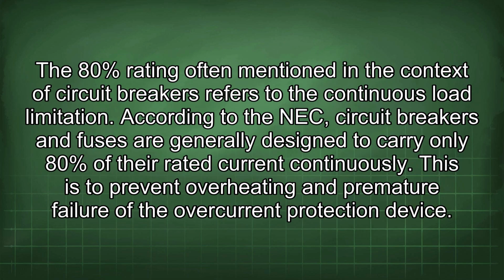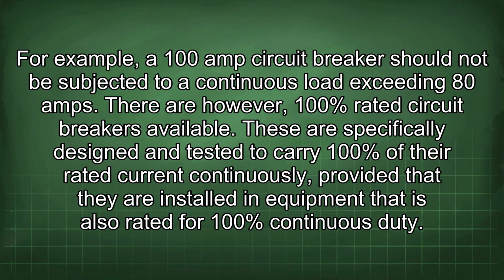The 80% rating often mentioned in the context of circuit breakers refers to the continuous load limitation. According to the NEC, circuit breakers and fuses are generally designed to carry only 80% of their rated current continuously. This is to prevent overheating and premature failure of the overcurrent protection device. For example, a 100 amp circuit breaker should not be subjected to a continuous load exceeding 80 amps.